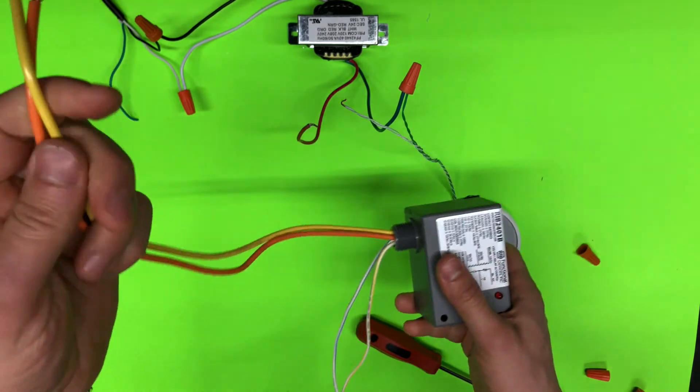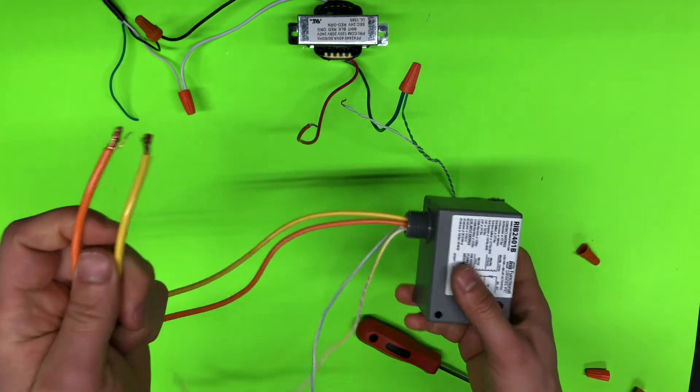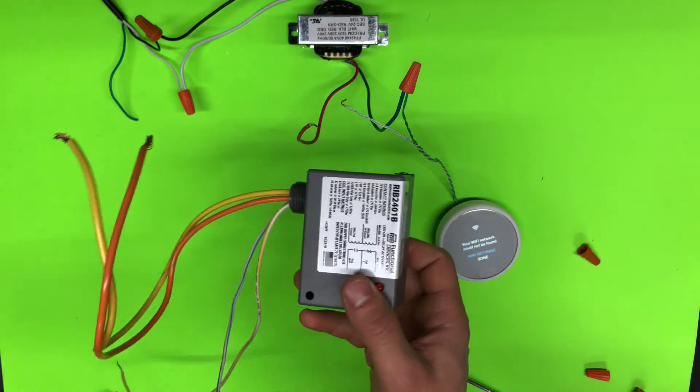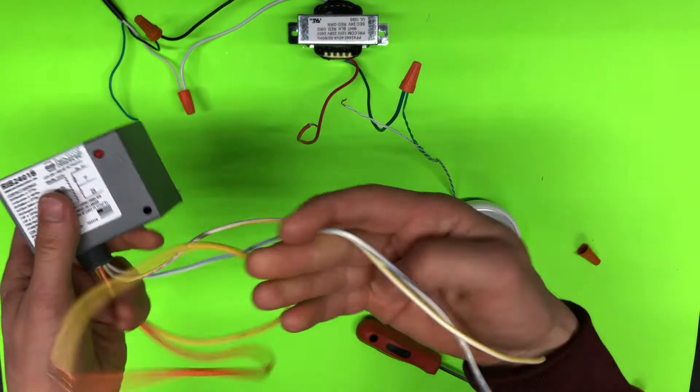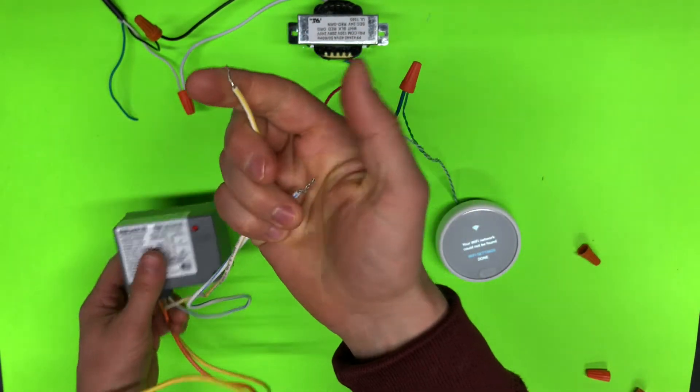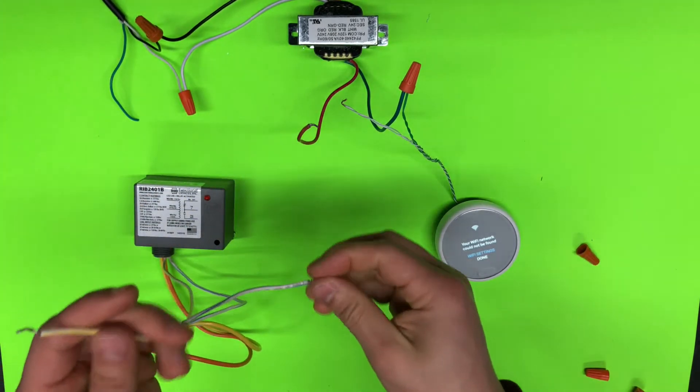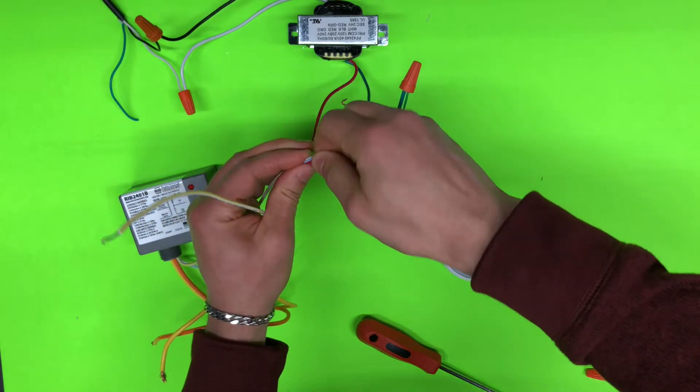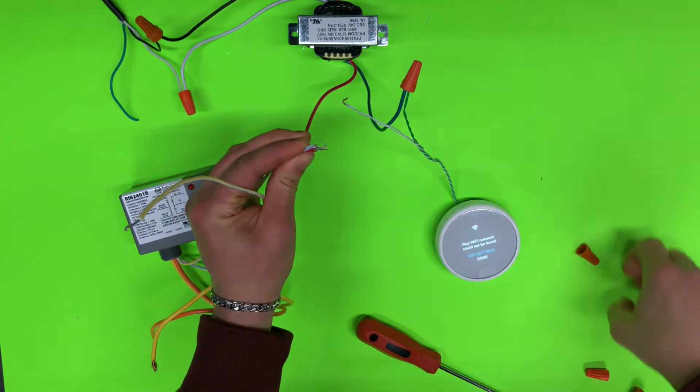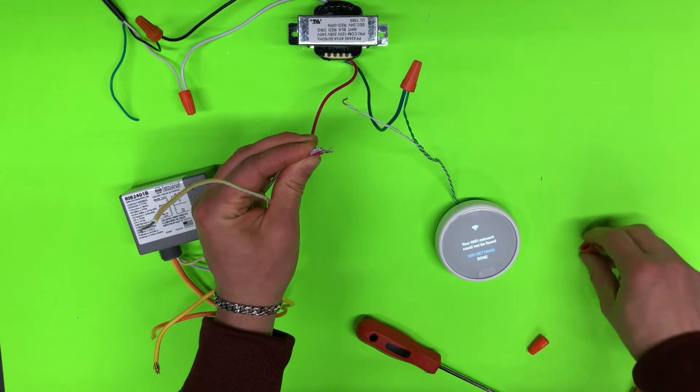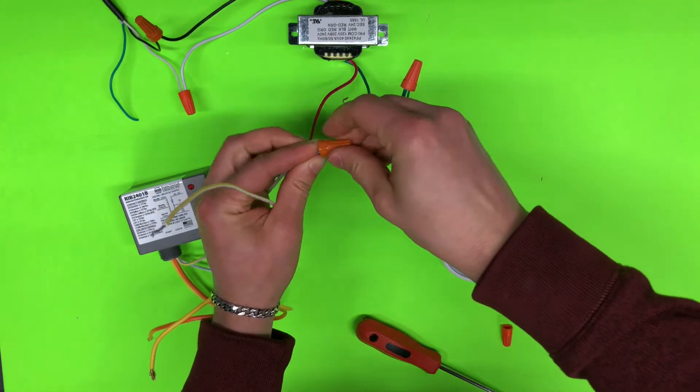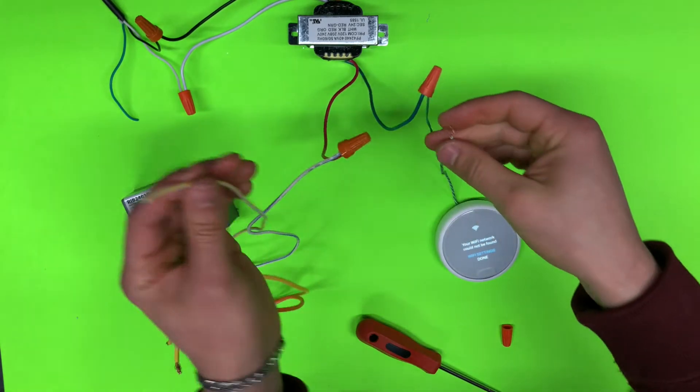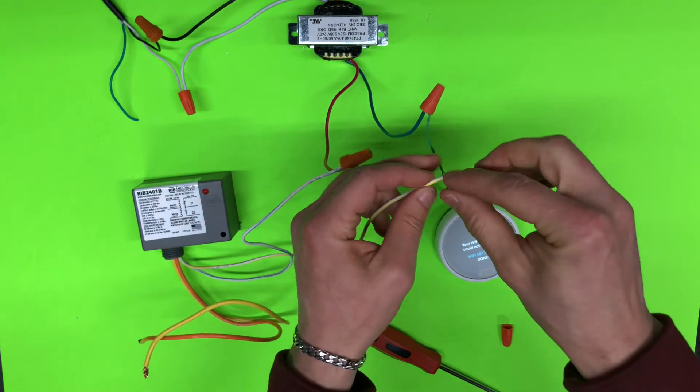Now we'll take our relay. We have two thick wires for high load, it can handle 20 amps, this is what we need for baseboards or for boilers. And this is the lower side, so we see thinner wires. So one wire we're connecting with our transformer, and second wire we're connecting with our thermostat.